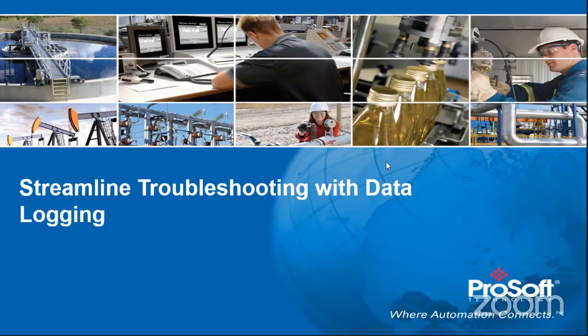And then we also allow users to record additional data on top of that. One user I have is recording drive gain off a Coriolis meter, and they want that as part of their archive data. Drive gain is not used in any of the calculations, but they're passing it over to the module. It becomes part of the archive structure so that they can look at it on the SCADA side or through FlowCal or different databases.